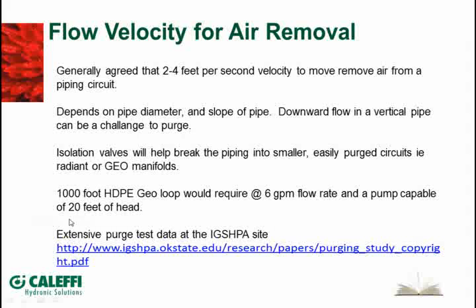And here's another example when we start talking about the geo loops and larger diameter, large bore piping, maybe 1-inch diameter high density polyethylene tube here on a big geo loop system. You're going to need to get about 6 gallons a minute through that, and that size loop is going to present about 20 feet of head. So you're going to need enough pump that you can get that flow rate, overcome that pressure drop, and be able to push the air out of those loops.